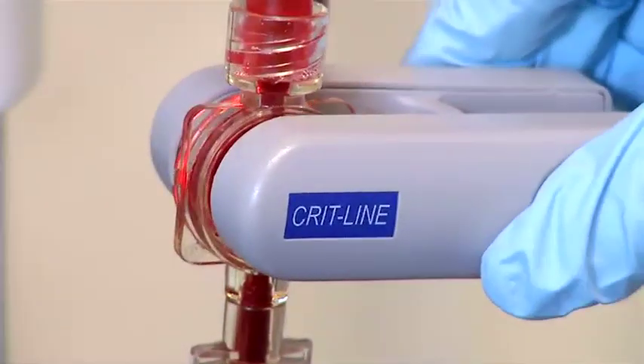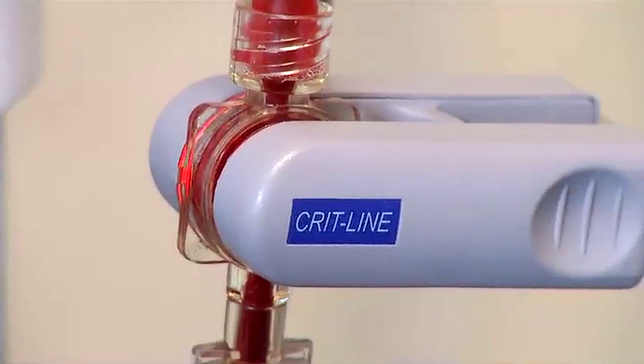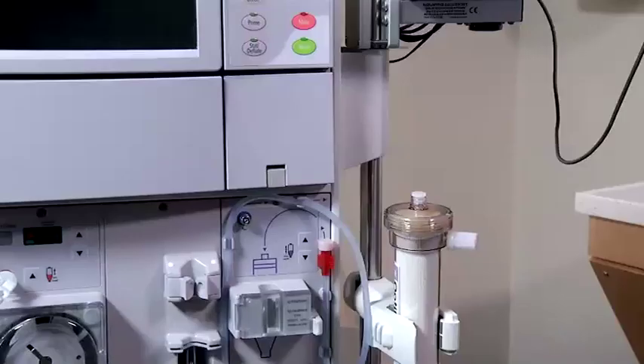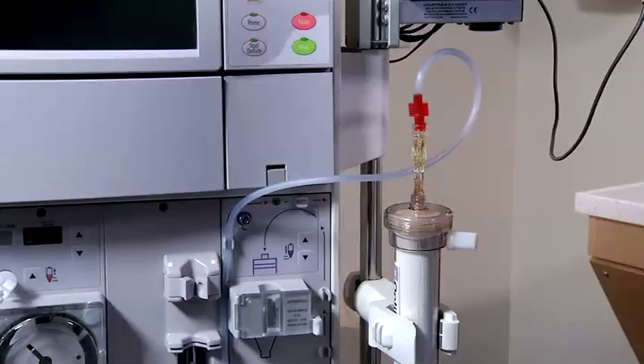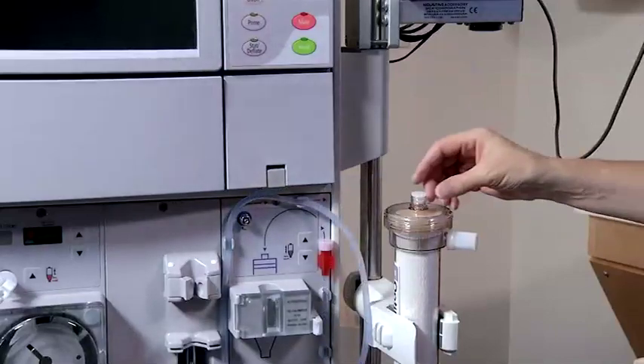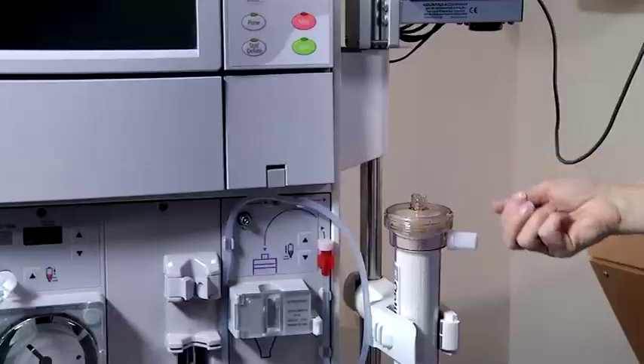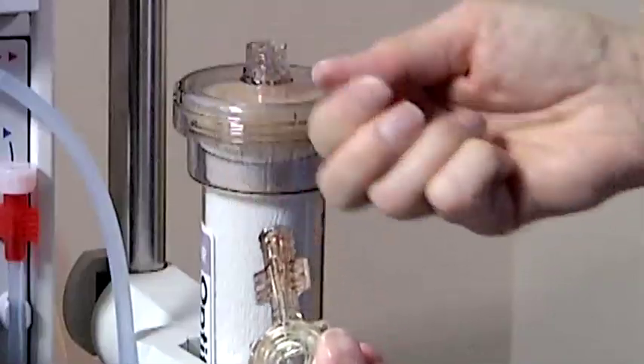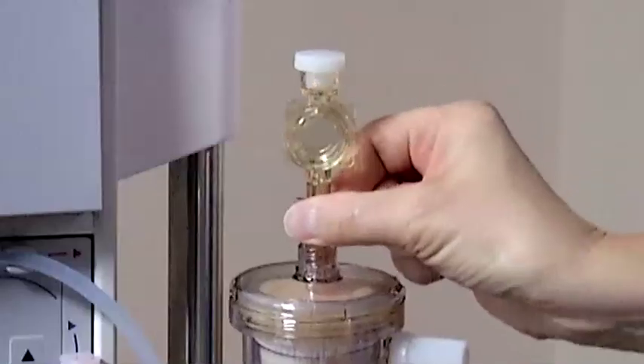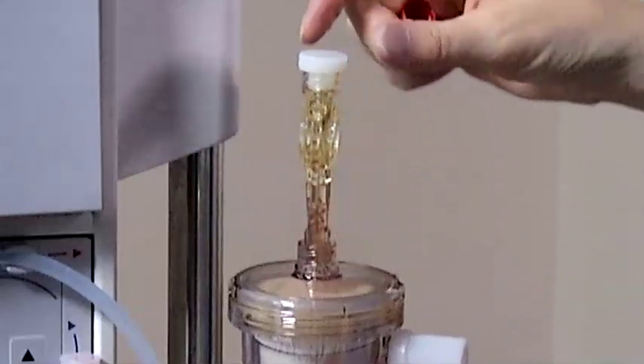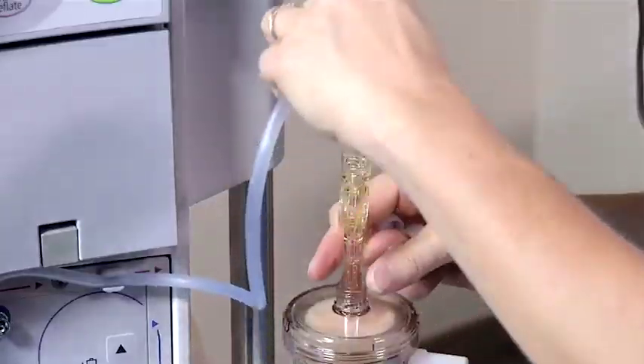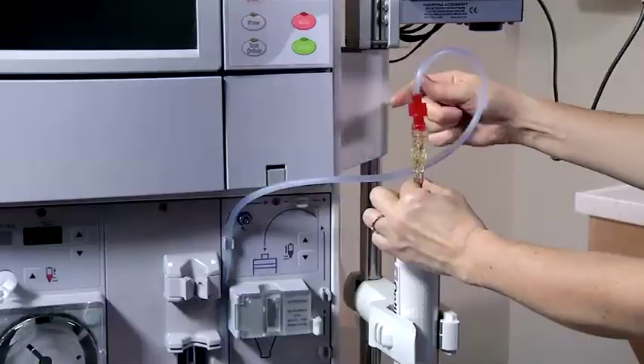The CritLine monitor utilizes a sensor clip which is placed on the blood chamber that is attached to the hemodialyzer. Proper alignment of the blood chamber and placement of the sensor clip is essential to obtain accurate readings. During setup of the extracorporeal circuit, attach the CritLine blood chamber to the dialyzer. Simply remove cap from arterial header of dialyzer and the red cap from the blood chamber. Attach the blood chamber by twisting the wing closest to the header until the connection is tight without using excessive force. Then attach the arterial bloodline.